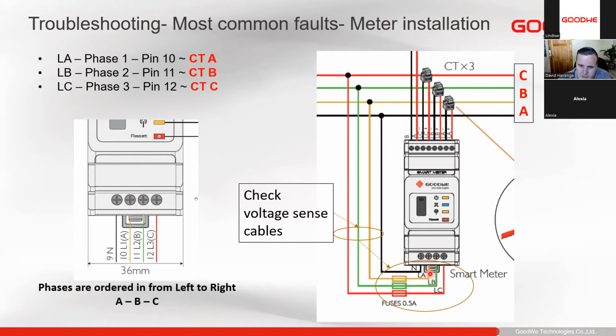So as you'll see, phase 1 is entering here, but phase 1 CT is over there. So please pay careful attention to installing this. The voltage sense, it's vitally important that the correct CT is in the correct direction with the correct voltage input. If you swap the voltages around, that CT will see all the current out of step, so it's out of phase, and then it will see it as a reversed value. So always make sure that the correct voltage sense to the correct CT is connected.